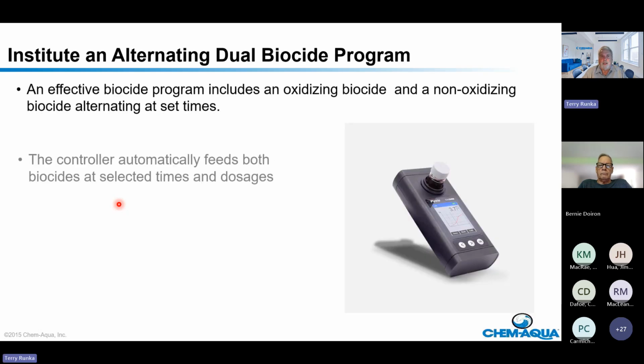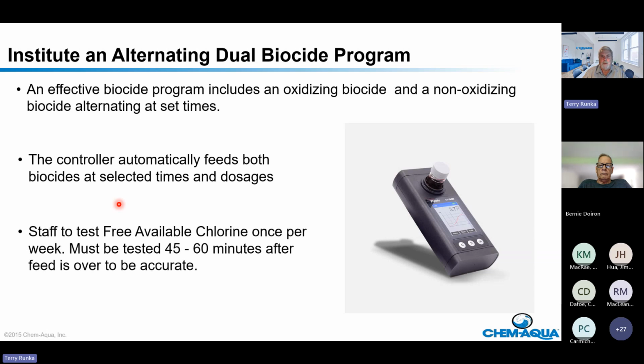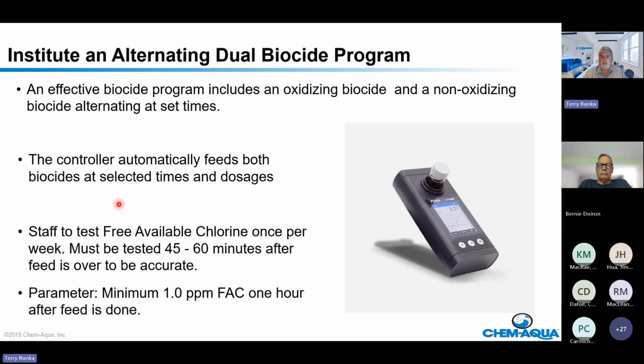Now, we've also instituted a dual biocide program. There's 2 kinds of biocides that are fed to a system. One is an oxidizer and one is a non-oxidizer. Oxidizing biocides are a bleach type, a halogen. They do 98% of the kill of all bacteria. They're like a big old flamethrower, and they kill all the bacteria, very effective against Legionella. But different biocides kill different ways. They kill different types of bacteria. So we alternate that oxidizer with a non-oxidizer. But the oxidizer feeds 3 to 5 times a week, 3 to 7 times a week, or continuous. The non-oxidizer is fed 1 to 3 times a week. And it kills in different ways.